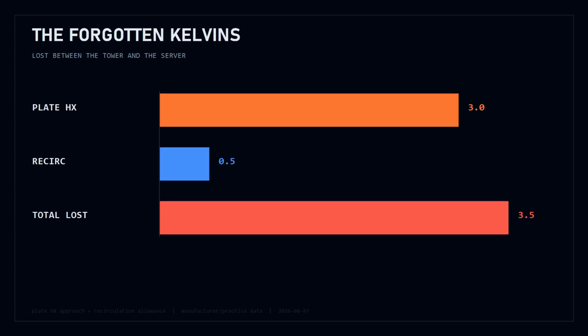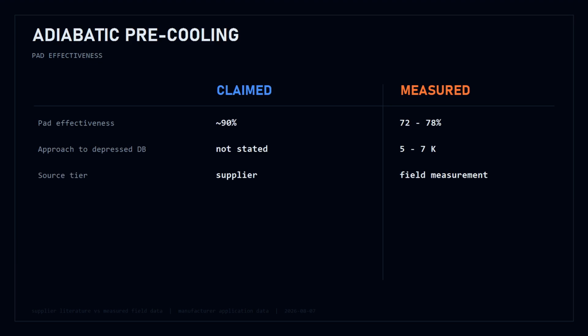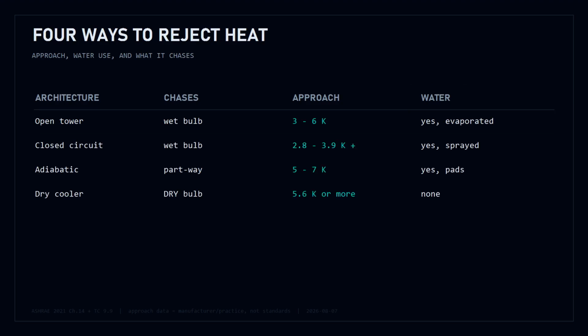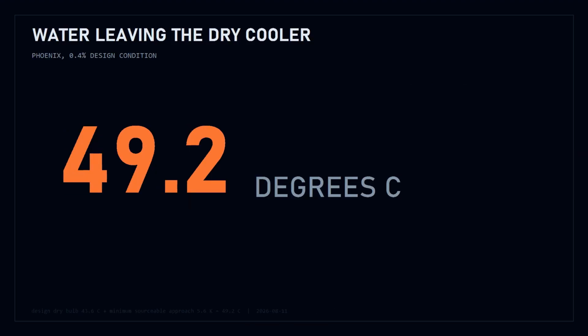An adiabatic cooler pre-wets the incoming air, dropping it partway toward wet bulb before it reaches a dry coil. Pads are advertised at 90% effectiveness, measured 72 to 78. And a dry cooler uses no water at all, which means it is not chasing wet bulb, it is chasing dry bulb and getting no closer than 5.6.